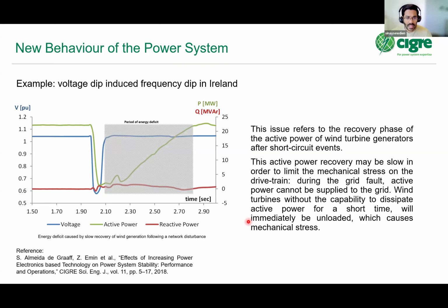So what's the issue here? You can see the blue line here is the voltage, and the green line is the active power. Ireland has a lot of wind generation, and I showed a figure before where they were hitting this 65% system non-synchronous penetration index. What happened in Ireland, and this is a true case, is that at a certain point in time there was a fault in the system. When there is a short circuit in the system, your voltage goes down. When the voltage went down, certain wind farms, mainly type 3 wind farms, reacted. There are 4 types of wind turbines, and this is specifically a type 3 doubly fed induction generator.